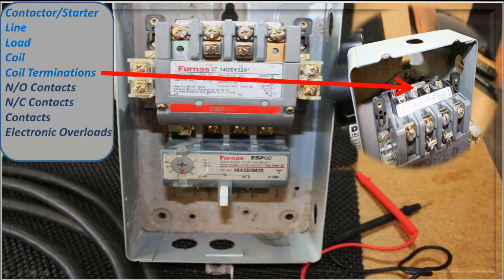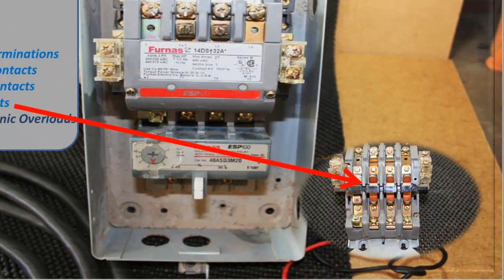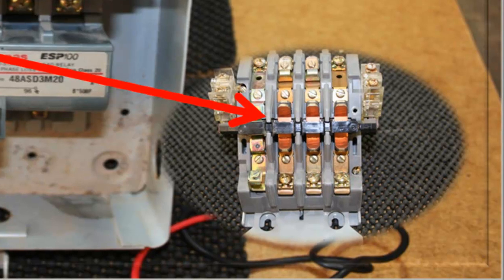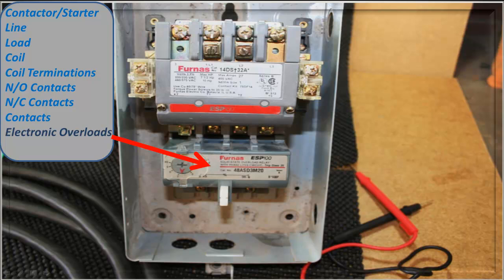The coil itself is the one that creates the magnetic field to pull the contacts in. The coil terminations are where you'd bring your 110-volt or 220-volt control source in. You have a set of normally open contacts and normally closed contacts — those are auxiliary, there for other items you want to control at the same time as your motor or equipment. I took the cover off where it says 'Furnas' and took a picture, so you can see the contacts on the inside.